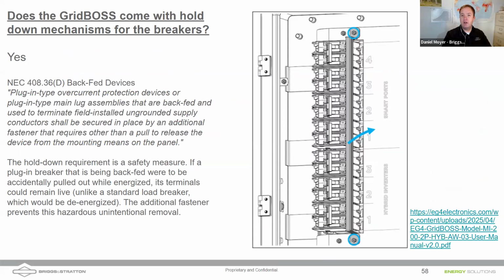Another thing I asked: does that GridBOSS come with hold down mechanisms for the breakers? Again, this is in code. So if we have a backfed breaker coming from an energy storage system, if the grid goes down and we're in a critical load subpanel, well, the hybrid inverter is going to disconnect us from grid, and we can use a backfed breaker to backfeed a load center. We might also come down on lugs, but if we have the backfed breaker, that's live, even if you were to turn it off and pull it off of the load center.